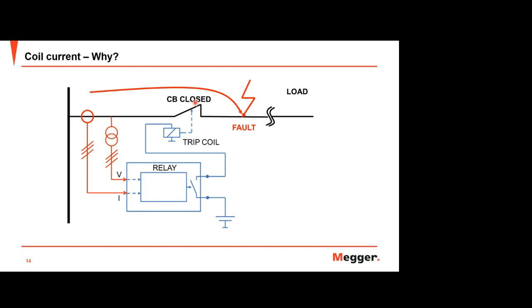Here you can see the breaker operates based on the relay, but of course it operates after getting a small trigger from this tripping coil, like this, and the breaker will open. After the breaker opens, it resets, the relay contact opens again, and the coil stops getting voltage. Actually, there is one small contact, contact 52a or 52b, that controls how long this coil can get the voltage from this relay. So this is the main reason, because the circuit breaker operates based on how the coil component works. If this fails, of course, the breaker will fail to operate.